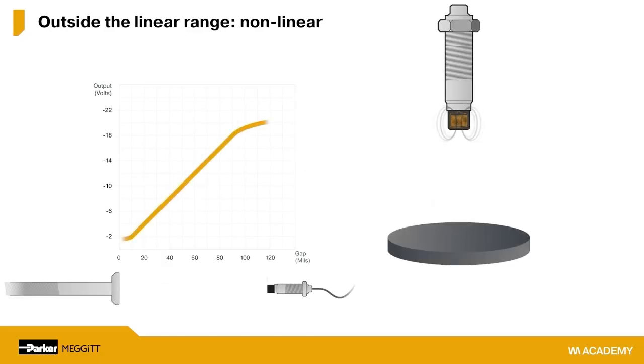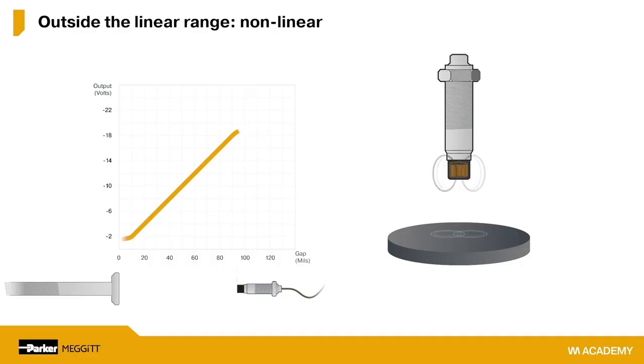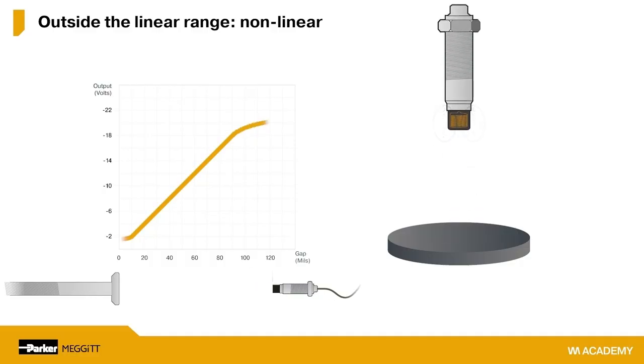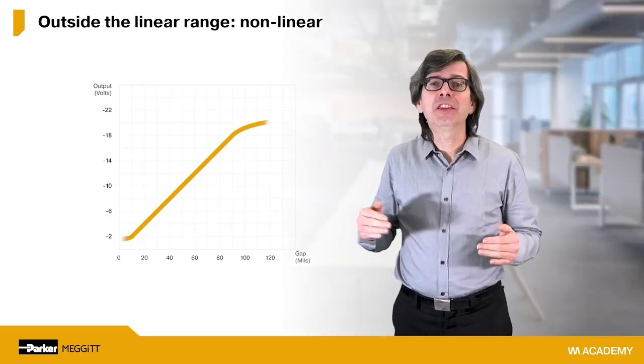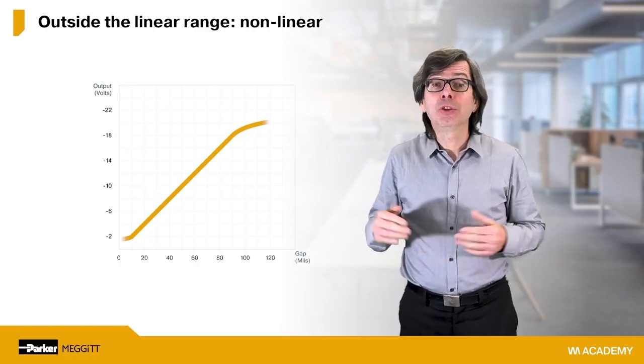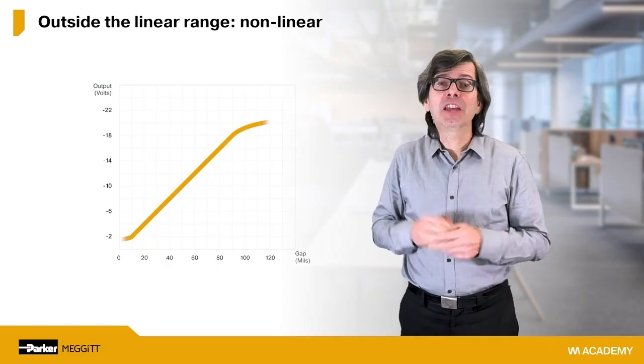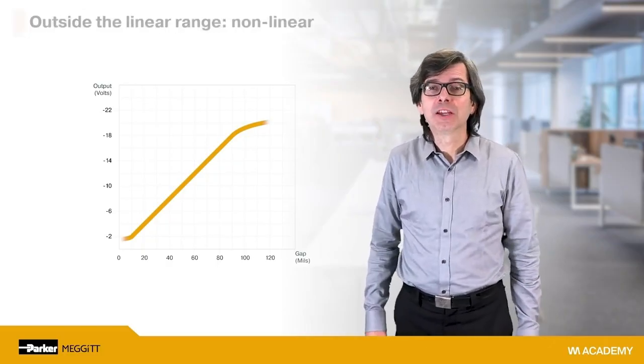At the other end of the linear range, above 90 mils of gap, an opposite situation occurs. Now the probe is so far away from the target that a change in gap does not give a proportionate change in electromagnetic field and corresponding eddy currents. Eventually, the probe is going to be so far from the target that it can no longer induce any eddy currents at all, and the output does not change. The output eventually saturates somewhere beyond minus 21 volts. Trying to operate in either of these upper or lower regions beyond the OK limits is really undesirable because the relationship between the gap and voltage no longer respects the published scale factor.